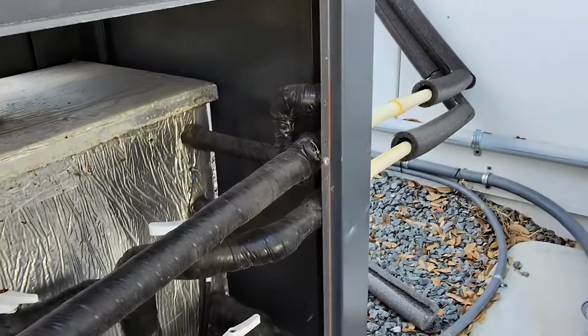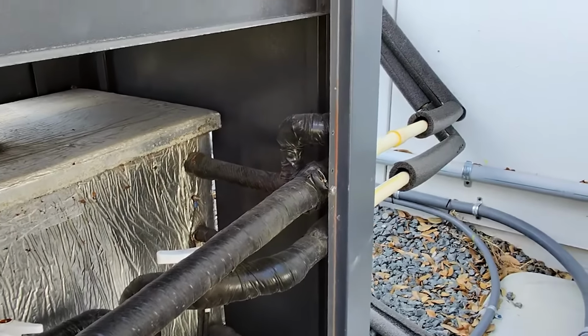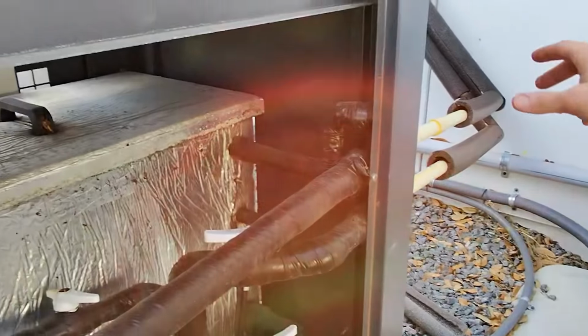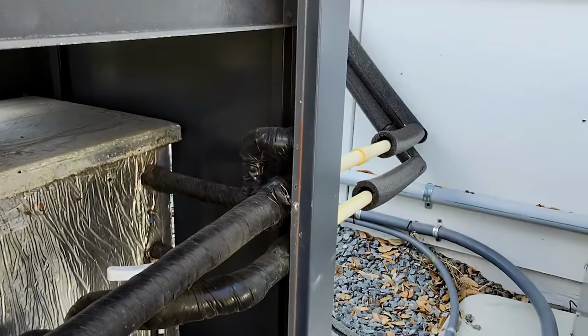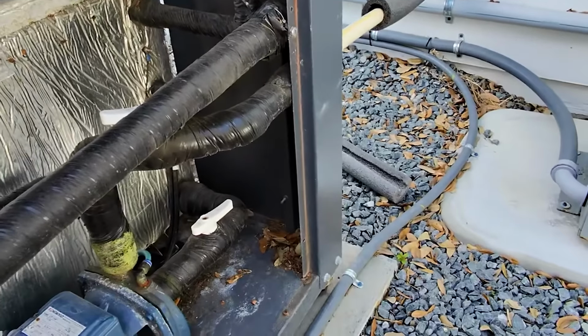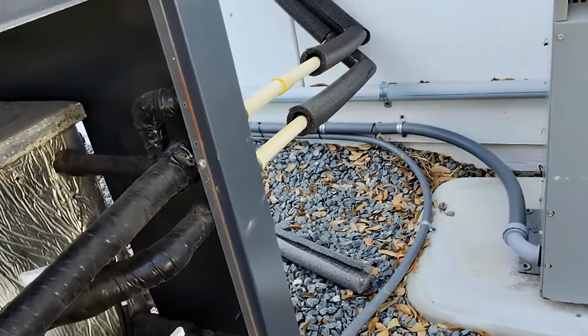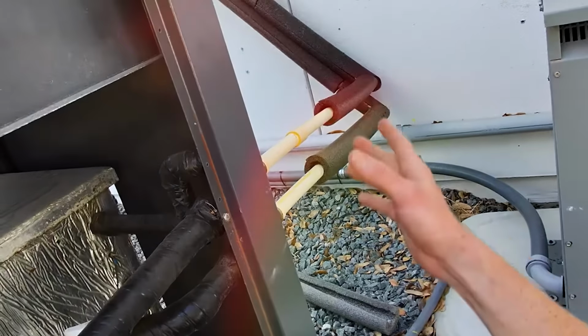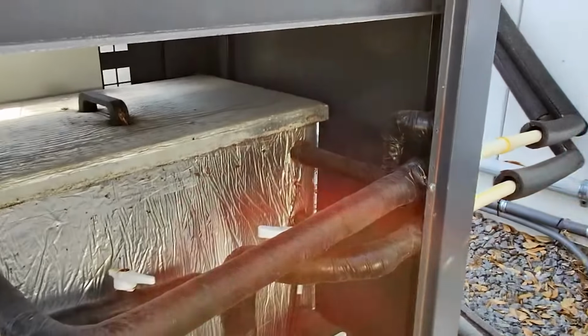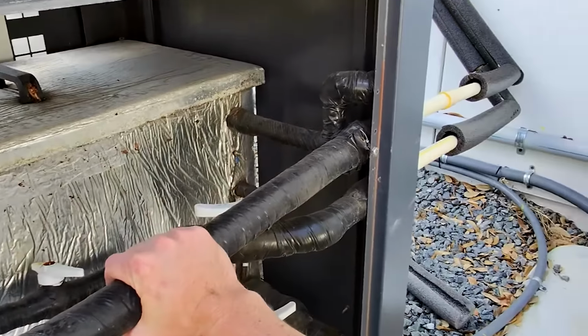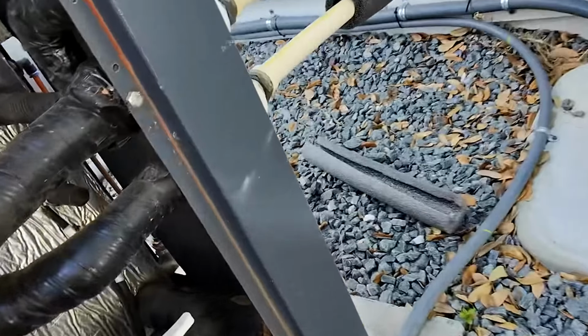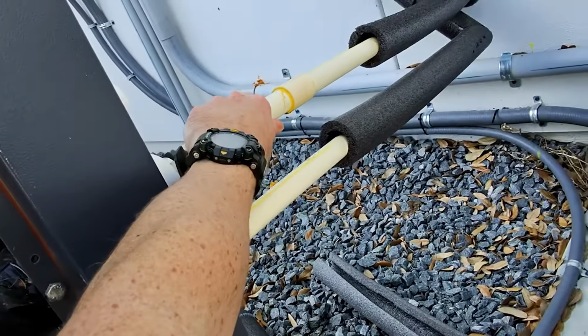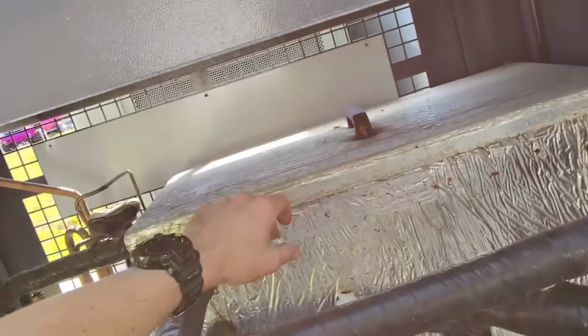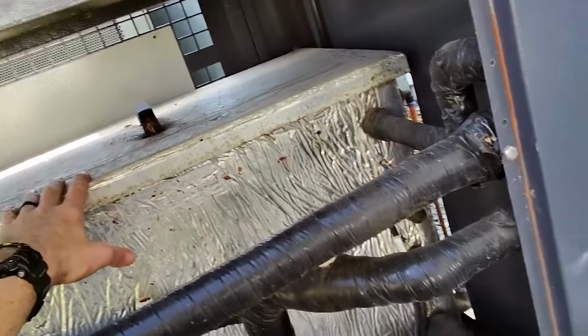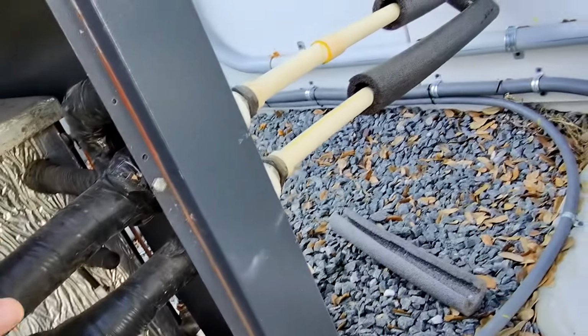So there is a whole separate system, which I'll show you here in a second, inside with multiple compressors designed to cool down a room to a negative 167 degrees, from what I was told, quickly. And it does that by allowing this system here to remove the heat from inside. So these water lines are actually almost too hot to touch, both on the inlet and the outlet. The tank, obviously, we've got steam once I open it up there, so that tells me that we are circulating water from inside to outside.